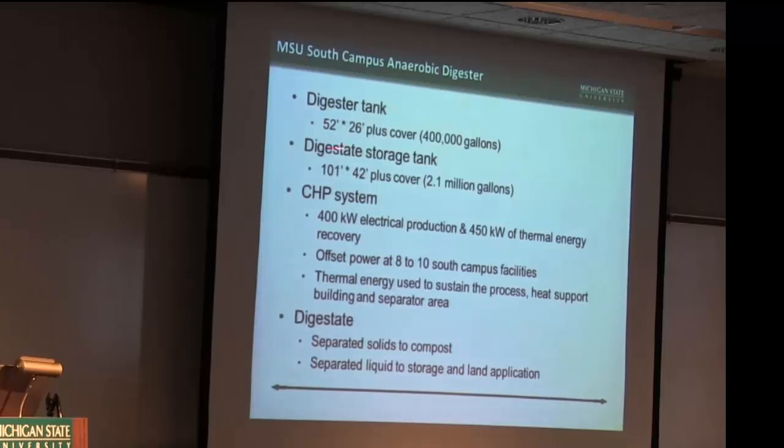This is a complete above-ground system, 400,000-gallon tank, that we call complete mixed. So in the plug flow, there's no mixing at all. We just pump material in, and it naturally is going to flow out to the outlet. Of course, you get separation and settling, and lots of things occur in that. This tank is circular and has two mixers in there at different elevations and with flexible angles. So what we call this crock pot should be stirred and should be homogeneous top to bottom, left to right, throughout.